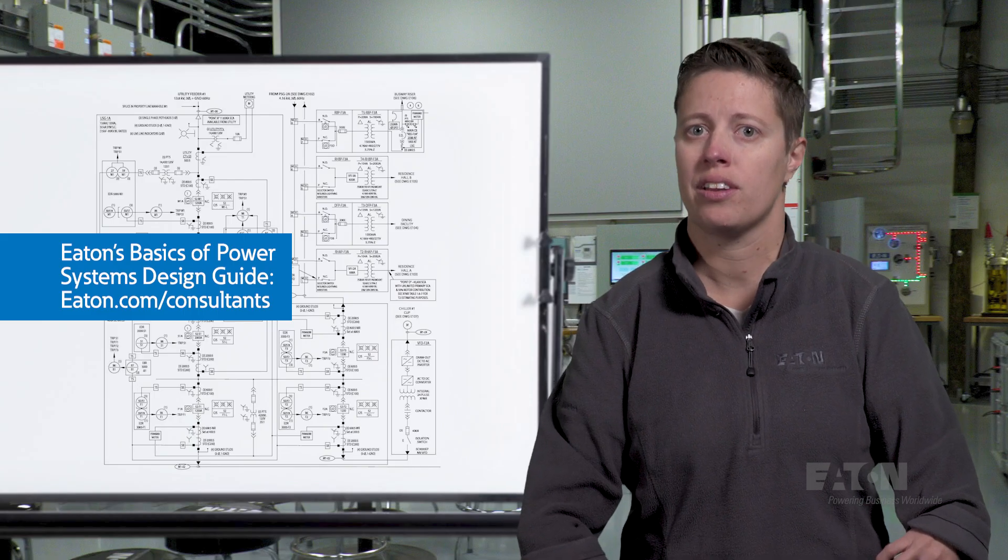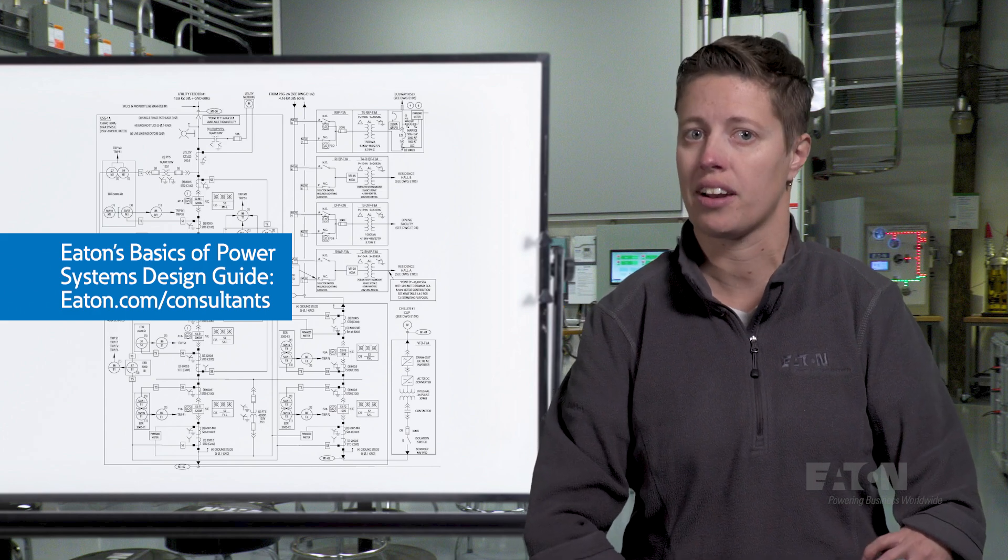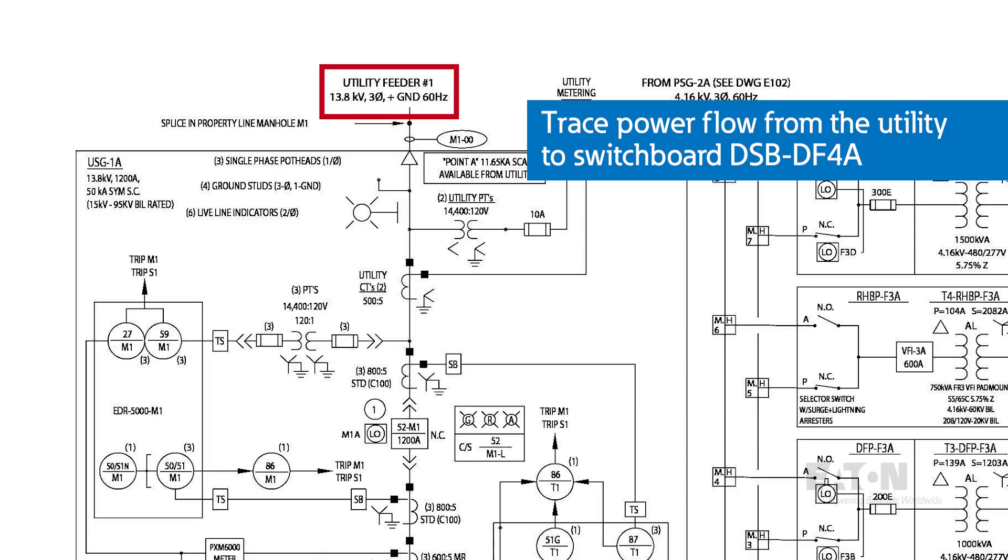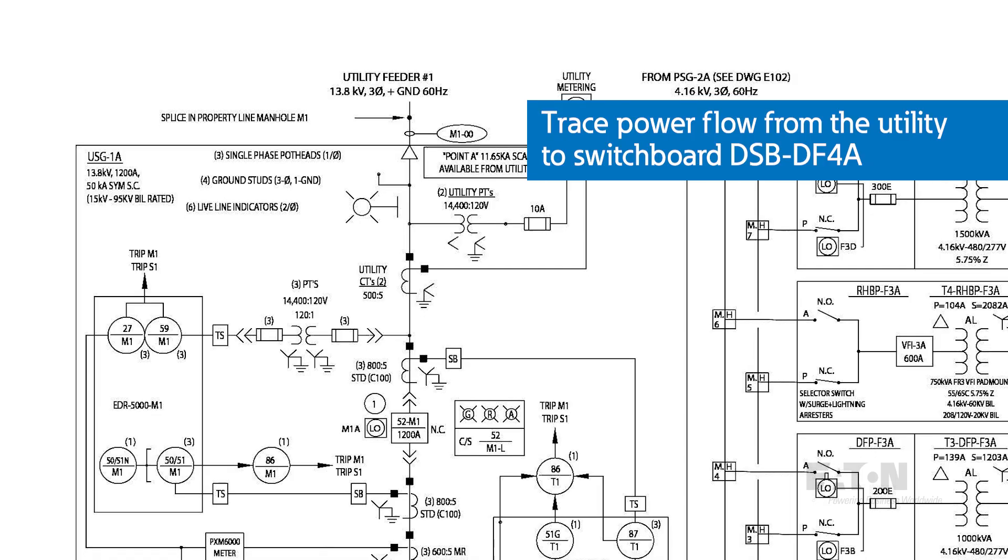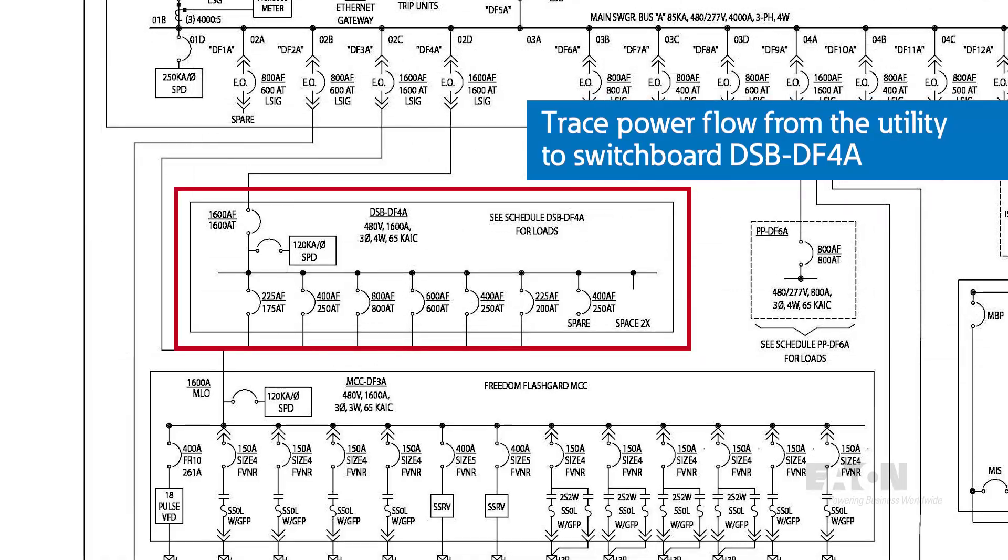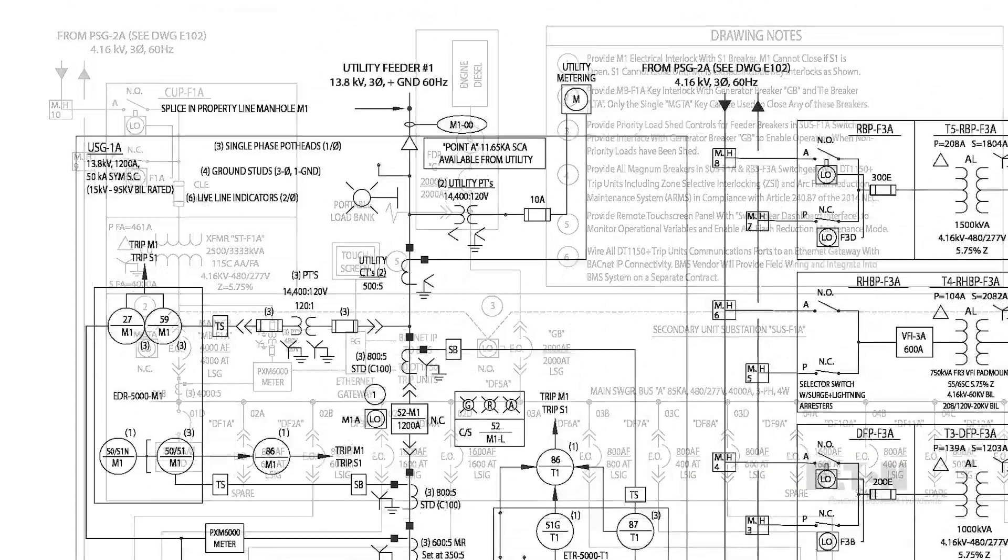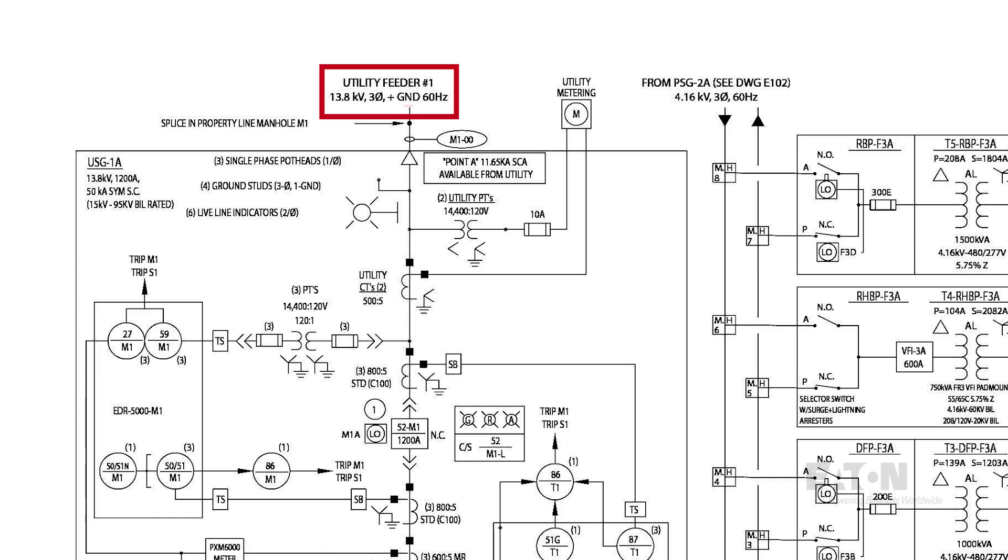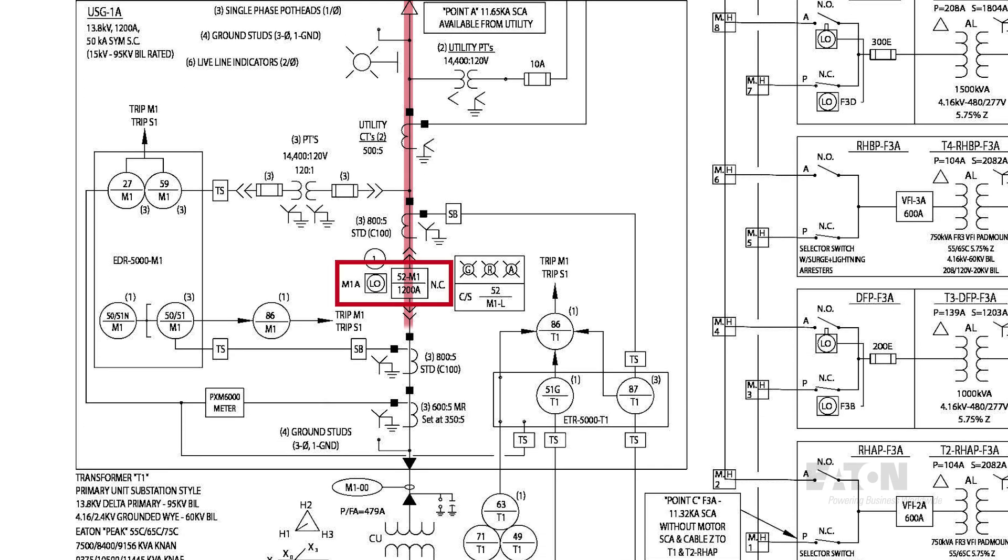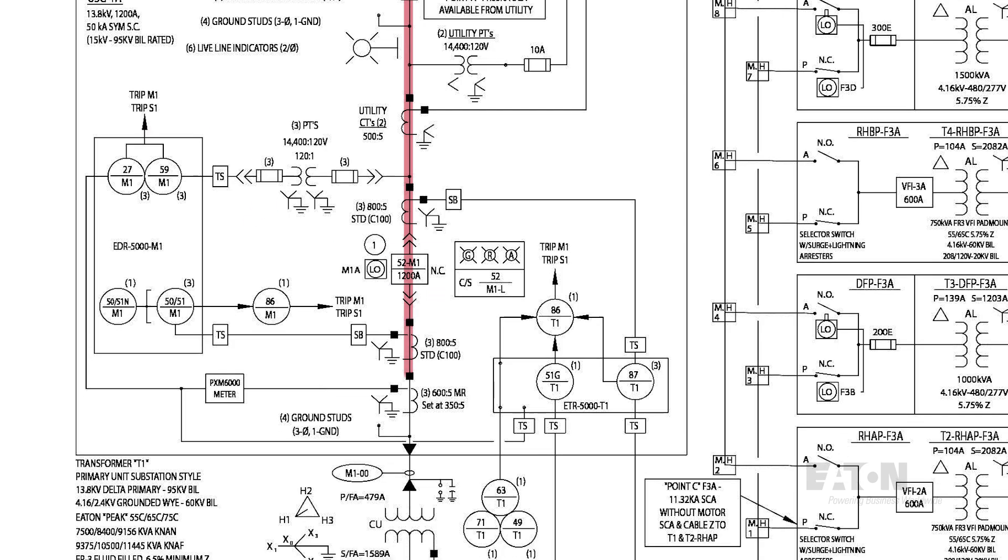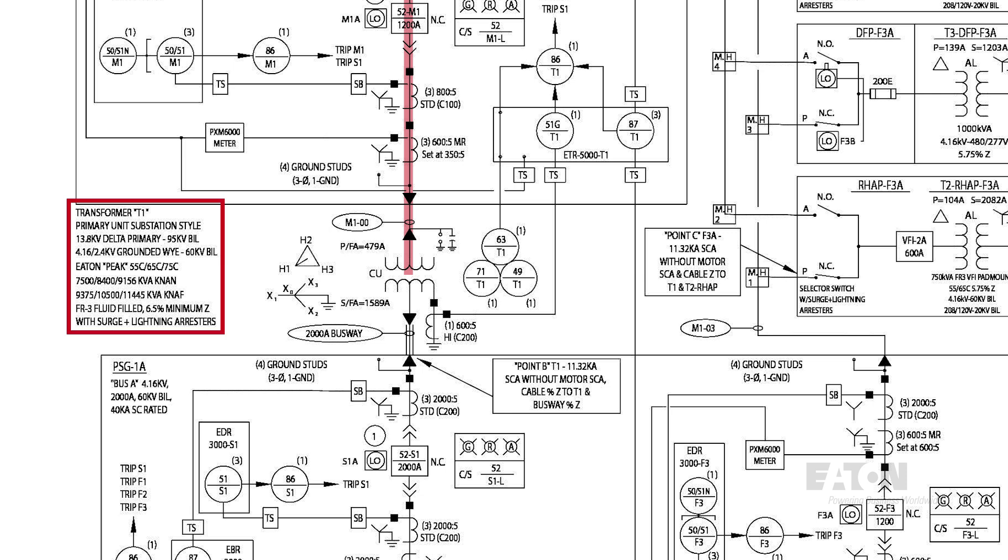Let's walk through a more complicated single line from Eaton's Basics of Power Systems Design Guide. We'll start at the utility and work our way down. Our goal will be to understand how power flows to switchboard DSB-DF4A. We can see that the utility power comes in at 13.8 kV from utility feeder number one. It comes into medium voltage switchgear USG-1A, which has 1200 amp bus. The power flows through this medium voltage breaker labeled 52-M1, which is protected by an EDR5000 feeder protection relay using CTs and PTs. The power flows to the primary side of transformer T1.